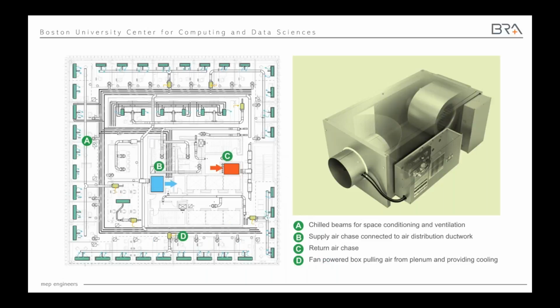And then on the floor, most people think of chilled beams as a great solution for ultra low energy buildings, but unfortunately there's one fundamental flaw with a chilled beam. In a typical chilled beam system, you connect the chilled beam through the ductwork all the way up to the main air handler. So if your air handler is not running, you get nothing at the zone in terms of heating and cooling. So let's say you're unoccupied for a portion of the building, you're still having to blow air into that space from the main air handler. And usually if it's a 100% outdoor air handler, you're actually ventilating those spaces that nobody's in just to maintain temperature. Like the sun is setting and it's pouring in the evening, but nobody's there. You're wasting a huge amount of energy.